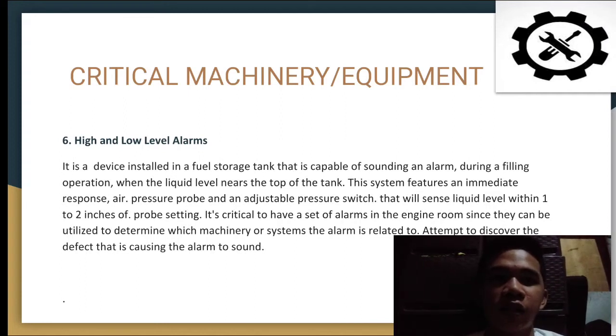It is a device installed in a fuel storage tank that is capable of sounding an alarm during a filling operation when the liquid level nears the top of the tank. This system features an immediate response air pressure probe and an adjustable pressure switch that will sense liquid level within 1 to 2 inches of probe setting.